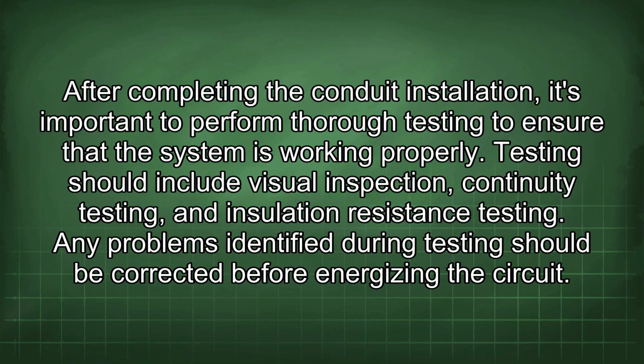After completing the conduit installation, it's important to perform thorough testing to ensure that the system is working properly. Testing should include visual inspection, continuity testing, and insulation resistance testing. Any problems identified during testing should be corrected before energizing the circuit.